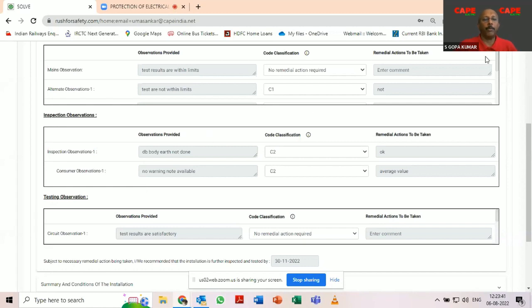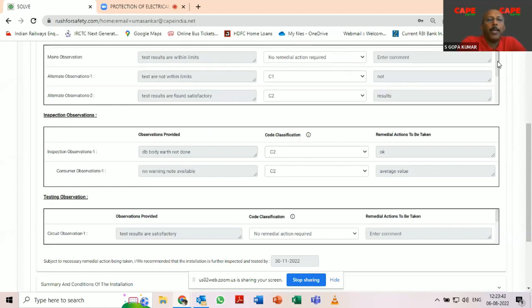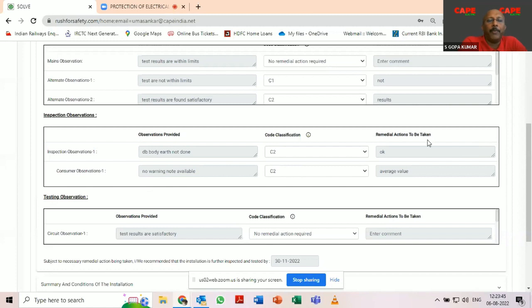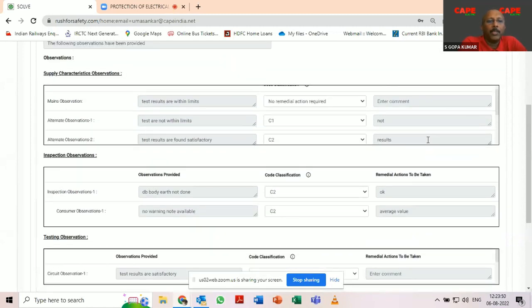Now, what you should understand is, as I explained in today's presentation about the lift, if you look at the IS 732 or IEC 60364, the standard format, information about lift is not included. Whereas in our software, what we are doing is the information about the safety requirement of all the connected loads. Let's say, for example, if you put a lift, then the standard says, okay, this lift is based on ISO 8000 part 2.